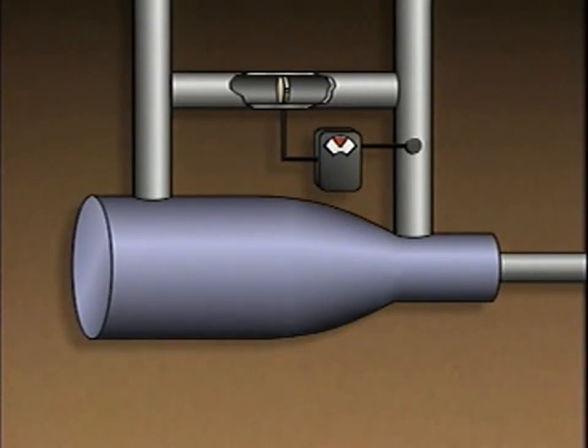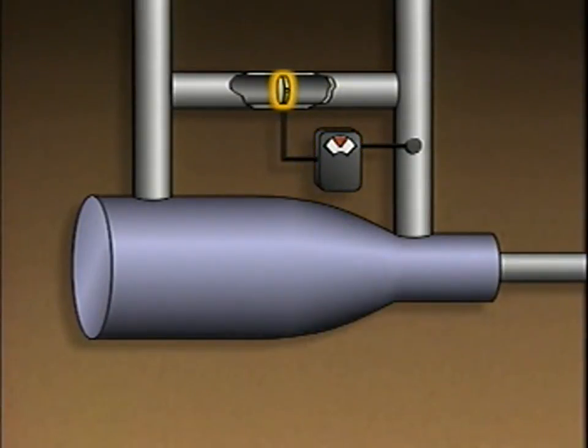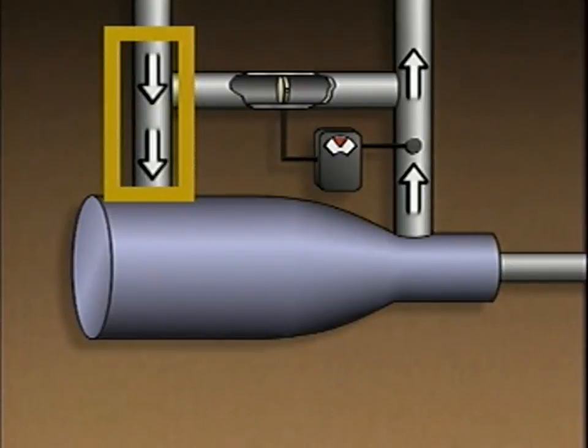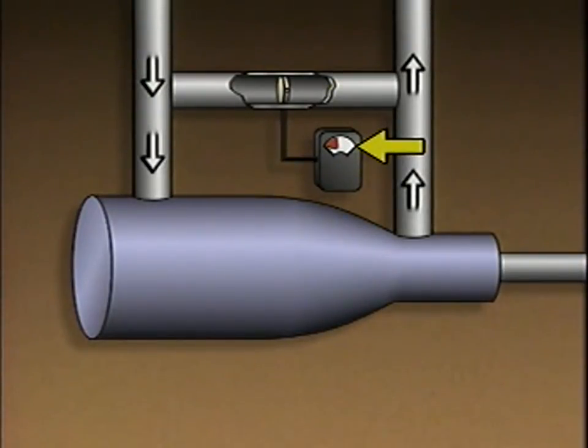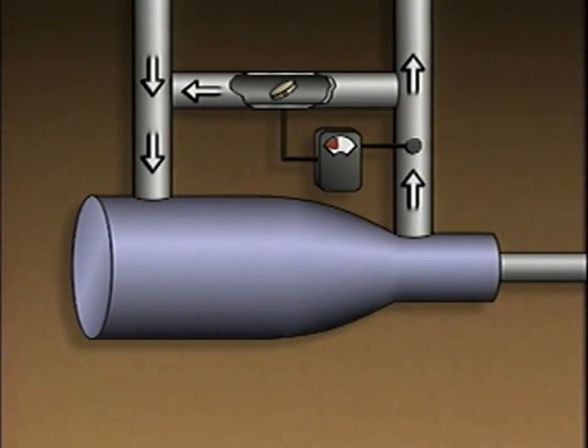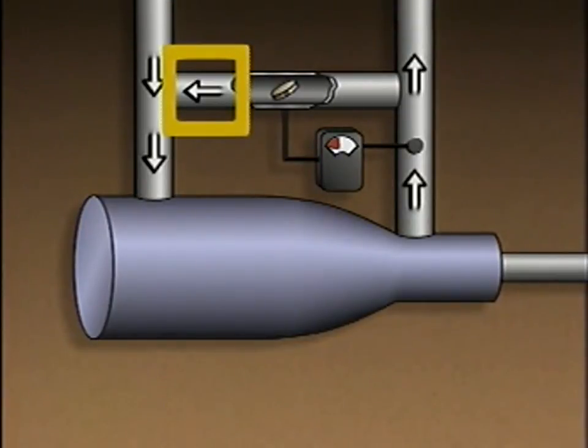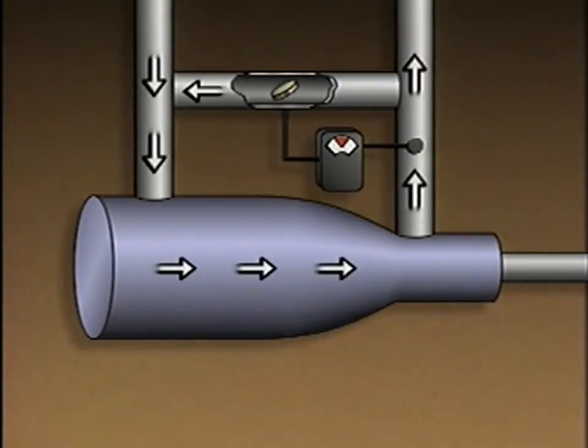This simplified illustration represents an axial compressor with a common type of surge control system. The control system consists of a flow sensor in the compressor's discharge piping, a flow controller, and a recirculation valve located in a section of piping between the suction piping and the discharge piping. When low demand causes the gas flow rate to approach the surge point, the flow sensor sends a signal to the flow controller. The controller then opens the recirculation valve and routes a portion of the discharge gas flow back into the suction piping, so the gas flow through the compressor increases and stays above the surge point.